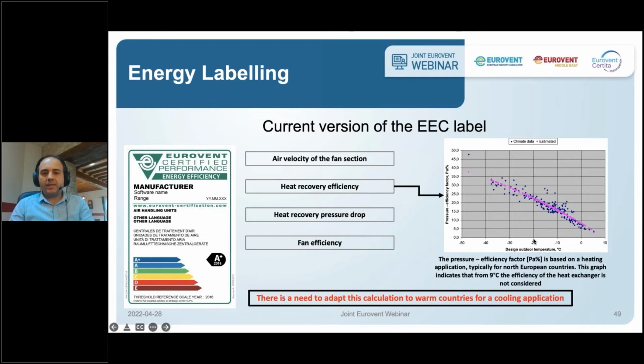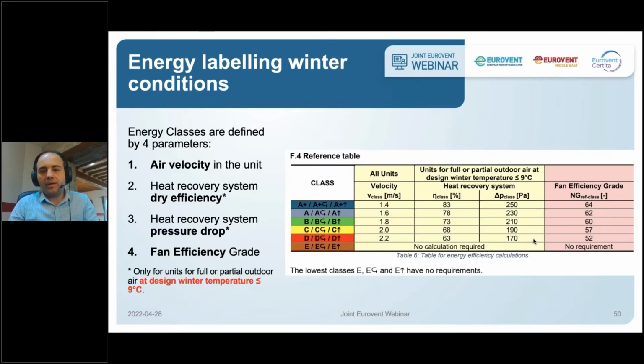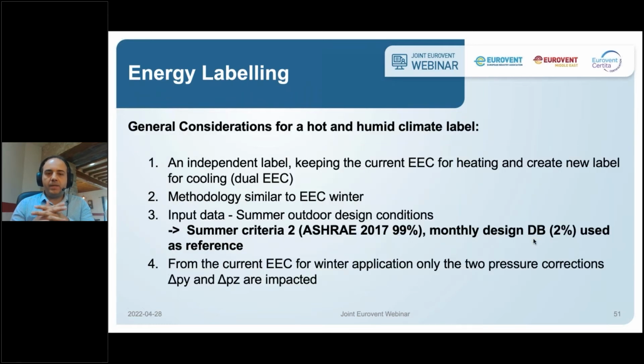So if you go to the next slide, you will see the table which defines the different energy efficiency classes. You have different thresholds for the 4 parameters: air velocity, heat recovery efficiency, heat recovery pressure drop, and fan efficiency. If all these parameters are according to this table, you will find the corresponding class. But you have to understand that you can have some compensation between the different parameters in order to reach a certain class.